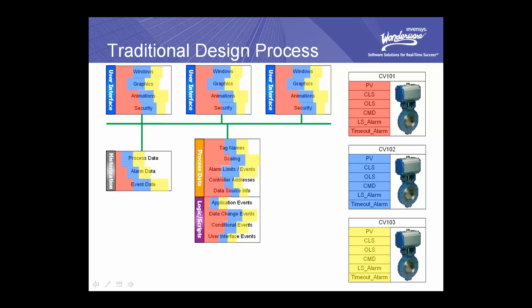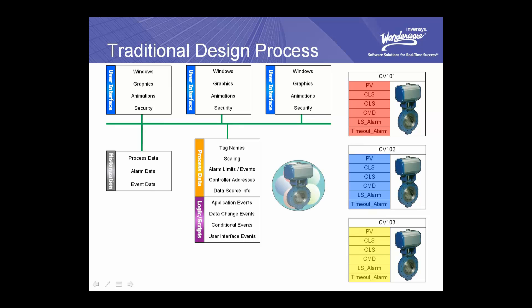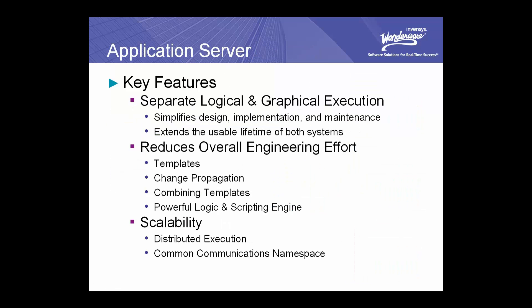What Application Server enables you to do is separate the components that don't belong together and combine the ones that do. With Application Server, you define a template that contains all this information: all the data points associated with the device, all the logic and scripting related to the device, all the alarms and limits, what should be stored in the historian, and even what graphics are associated with the device. Because these templates contain all the information necessary to define the device or asset, we realize significant reductions in the overall engineering effort — because you're not recreating the wheel every time you add another device or valve to the system.